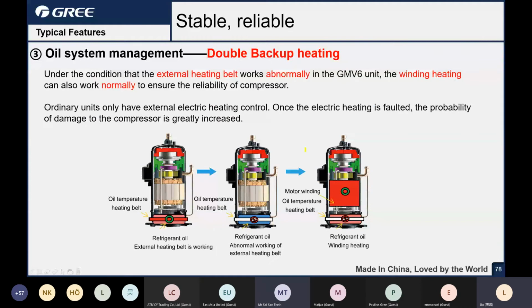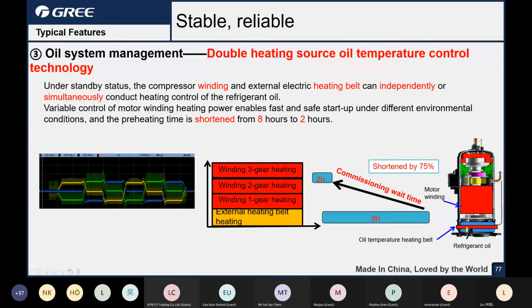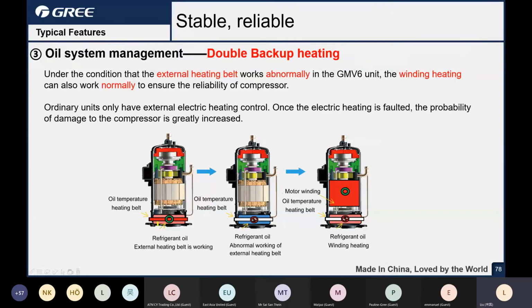Next one is the double backup heating. Double backup heating. So what does it mean? For the ordinary compressor, there is only one preheating belt. Only this one, right? If this one is faulty, how can the compressor get preheating? But in GMV6, there is a backup. If the external heating belt is abnormal or faulty, the unit can use the winding as a backup heating for the oil. Okay, so that's really good for the reliability of the running of GMV6.